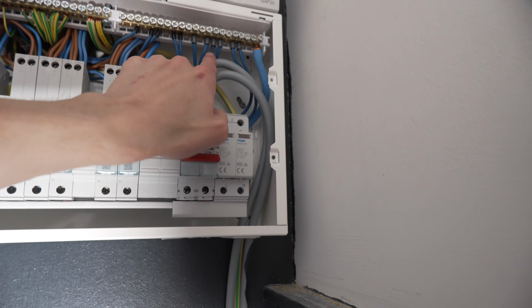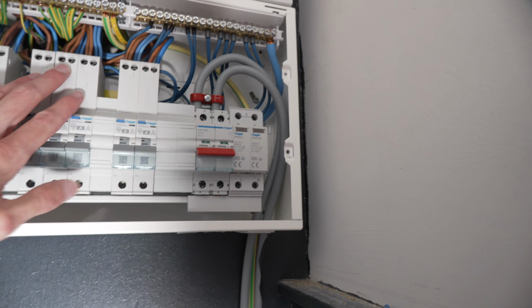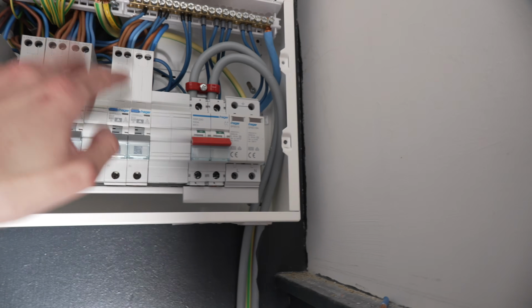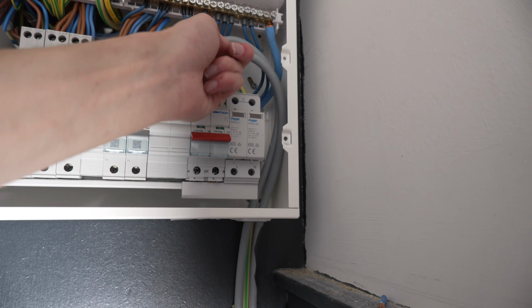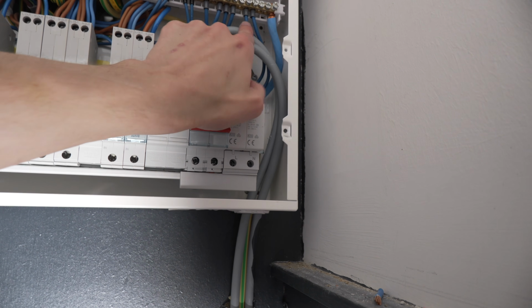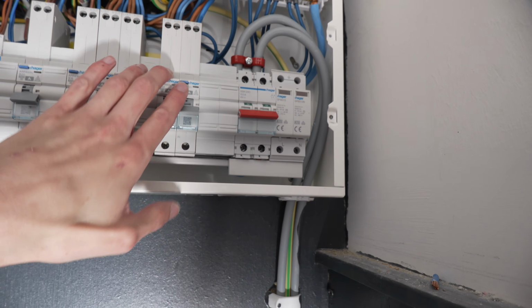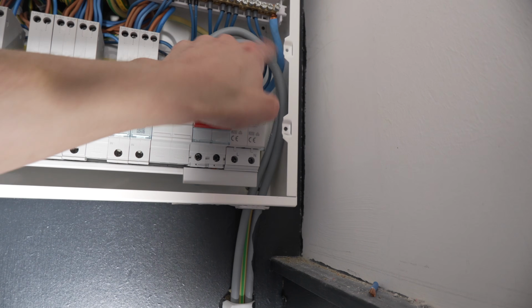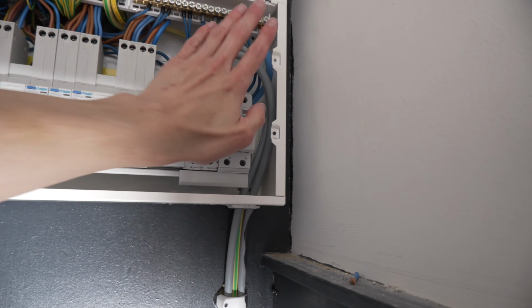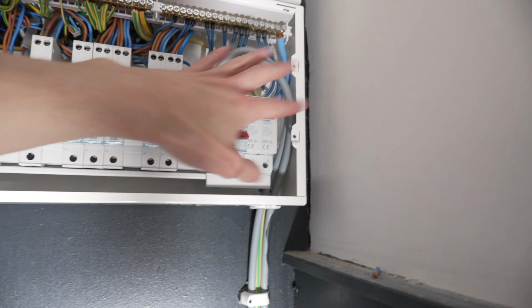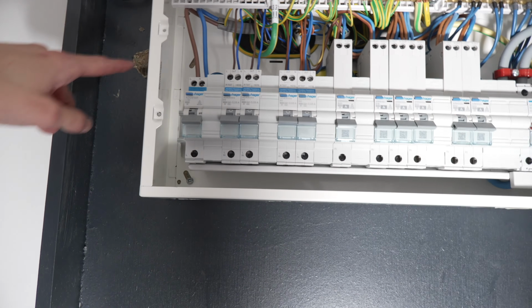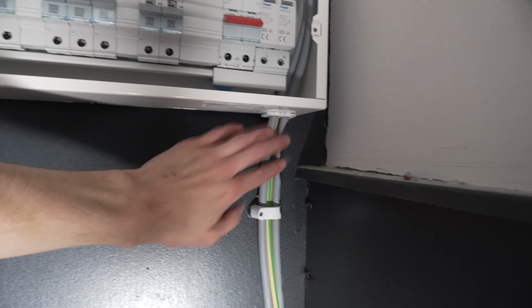So these three neutrals here relate to the socket circuits, and these two neutrals here relate to the kitchen. So I put one CT around these three and one CT around these two. That will handle the sockets and the kitchen circuit. And finally we have the grid CT that can just go onto one of these 2 meter tails over here. I'll see how I'm for space fitting that CT into the board. If it's just too tight, I can always bring it out of the board and put it onto one of the meter tails outside of the board instead, but we'll figure that out.